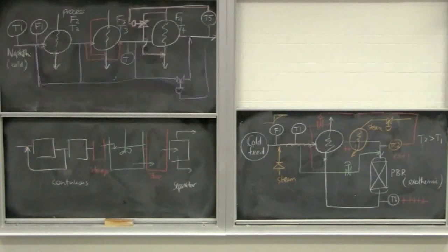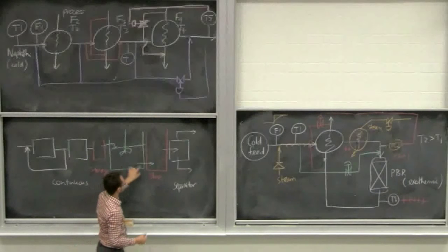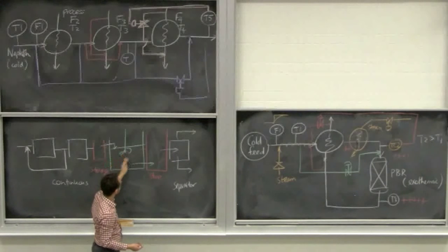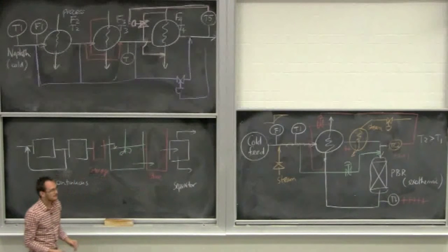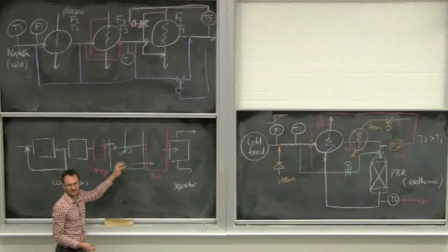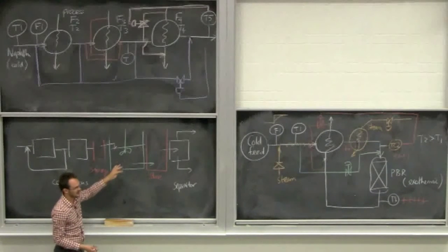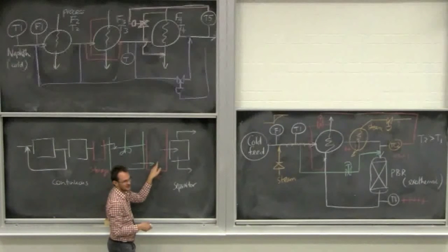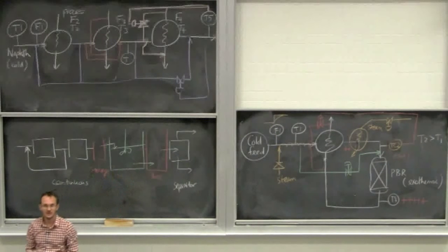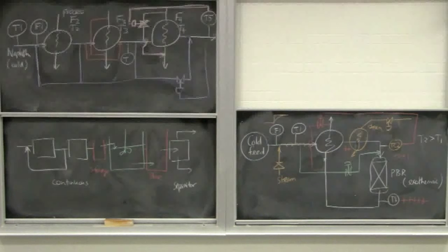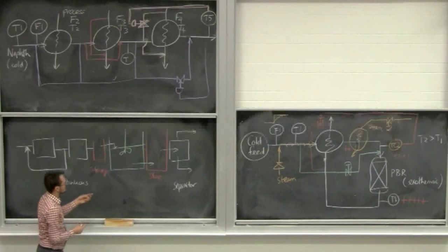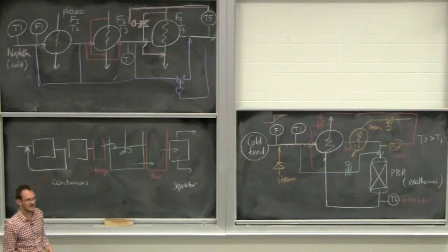It's moved from there into the storage. And then downstream, I can now continuously operate my separator after that storage unit. And typically, that storage afterwards is the size of your batch reactor plus more. Because what we want to do is, once this batch is finished, we're going to transfer the fluid over into the store. And then clean my batch. There's often a cleaning process that takes place on the batch reactor. That's going to take up some time. And while that batch is being cleaned, I'm still consuming the material in my store. So you need to be able to hold not only the batch, but a bit more than that to modulate that disturbance, okay? So this is not uncommon. We often see the batch process stuck in the middle of a continuous part on either side. Okay? So that's another important point related to operability. Why does the second one need to be filled?